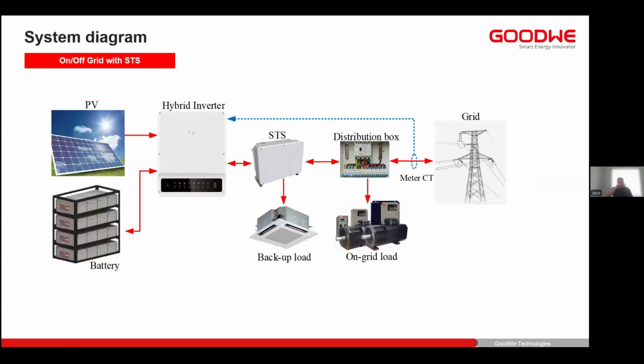A typical system diagram. So this is for an on-off-grid scenario. So you have your DC inputs on the left, PV input and the battery input. Then from the output, the AC output, we'll go to the static transfer switch. On the static transfer switch, you have a grid port for your grid connection. And then you have a dedicated backup output port. And then the on-grid loads will connect directly to the distribution board. So that's for the on-grid loads or the non-essential loads. And then one monitoring meter with the CT clamps to enable grid export limitation, as well as full monitoring on the grid.